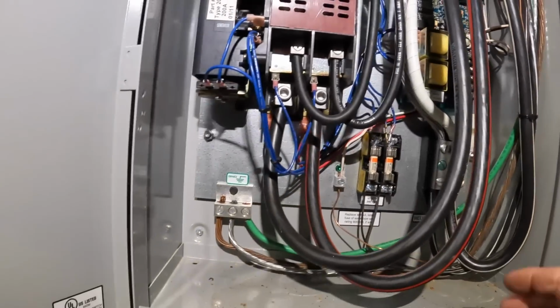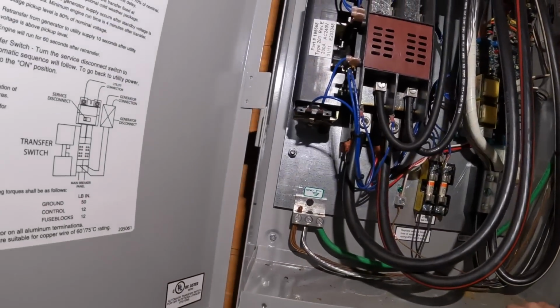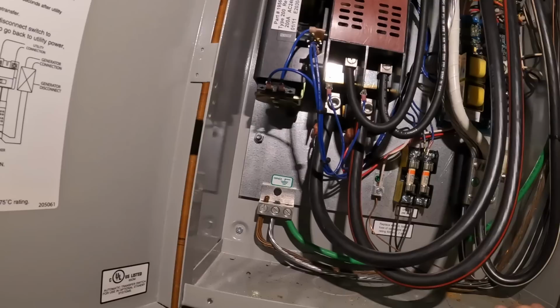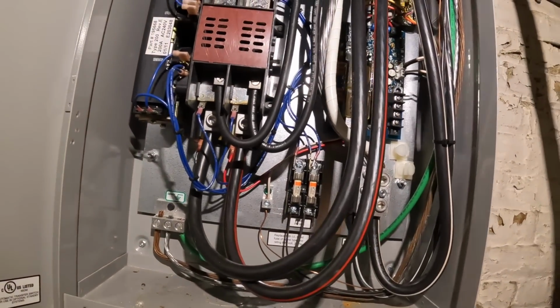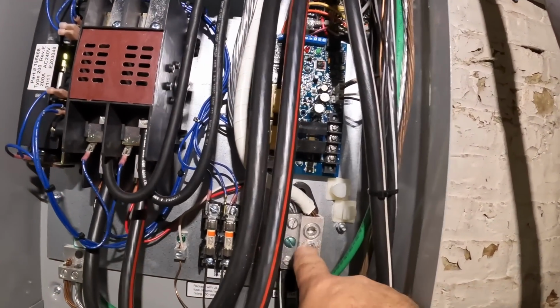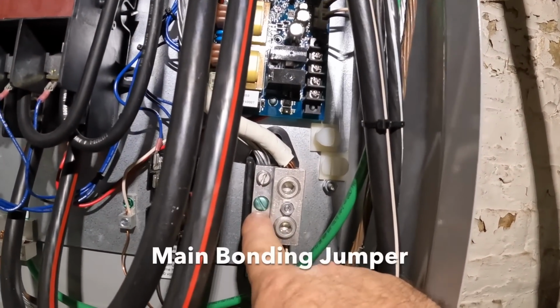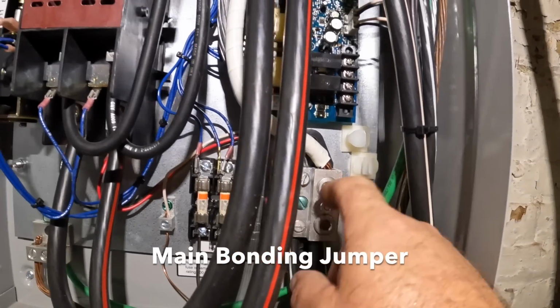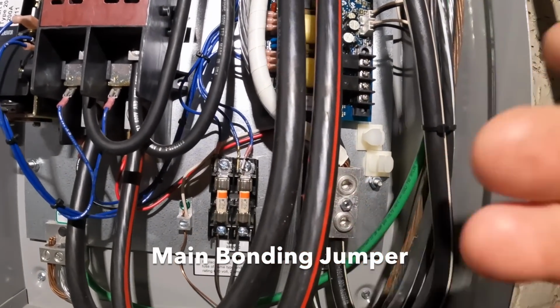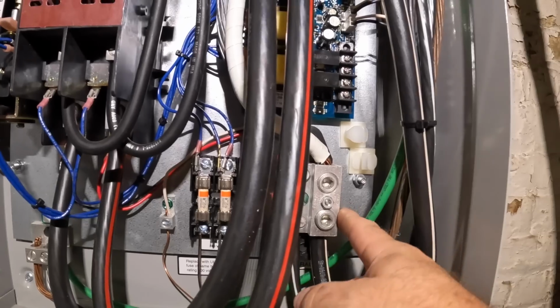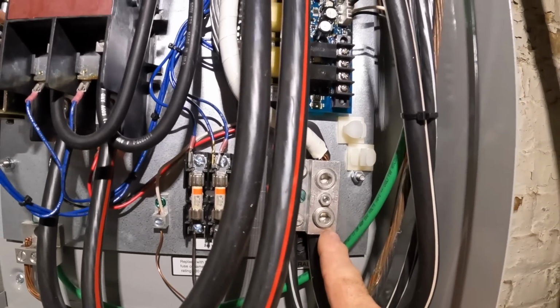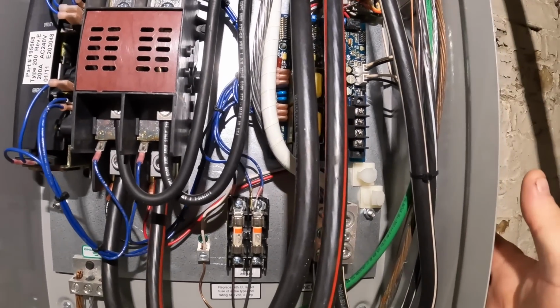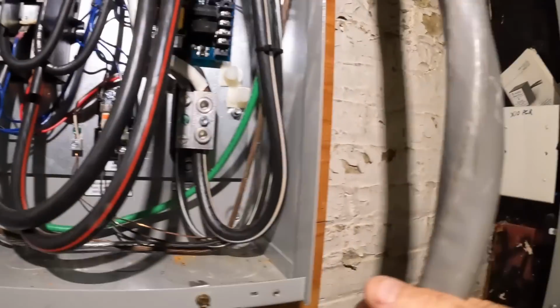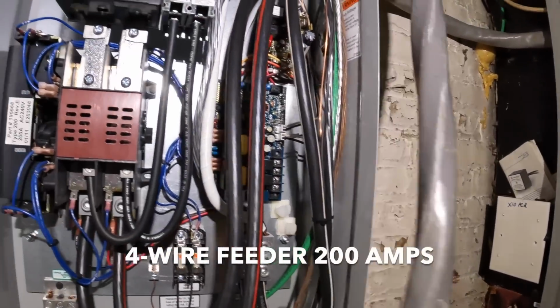Then we're going to bring our ground. It looks like I might have to get a lug for the ground here, because this is my neutral block. Then we're going to remove this bonding screw, so this neutral terminal block will be independent of the enclosure. That's why we ran four wires in our service entrance riser cable.